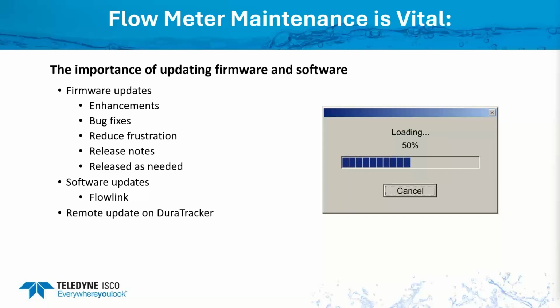Now, one other important factor for your flow meter maintenance is making sure you have the latest software and firmware updates. And so, with your cell phones, they're always sending out updates. We're no different. The firmware updates will provide enhancements to the equipment and bug fixes. It's going to reduce frustration, because if we already have a fix for it, and you're still struggling with something, might as well fix it right away, get past that, have everything running correctly. When we send out a firmware update, we do have release notes, so you know what changes we've made.